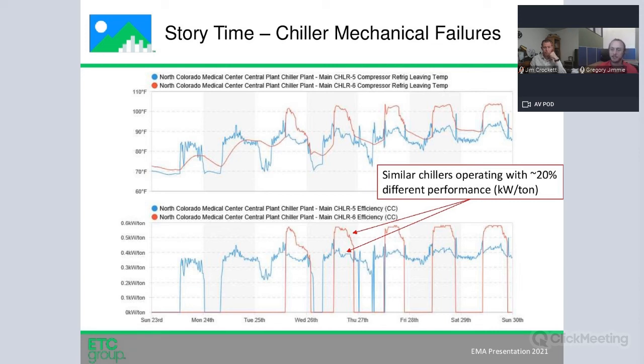So this is kind of like story time I have called out here. It's not always about set points. It's not always just about resetting your chilled water temperature to be warmer or resetting your condensing water to be colder. Those are great places to start, but there's a lot of devil in the details. There's other things that will happen, and a common misconception is, hey, I'm meeting my chilled water temperature set point, so my chiller is good. I get it annually serviced. It's as efficient as it's going to be, but that's not always the case. There's a lot of things that will go unnoticed because you're still meeting that chilled water temperature set point.